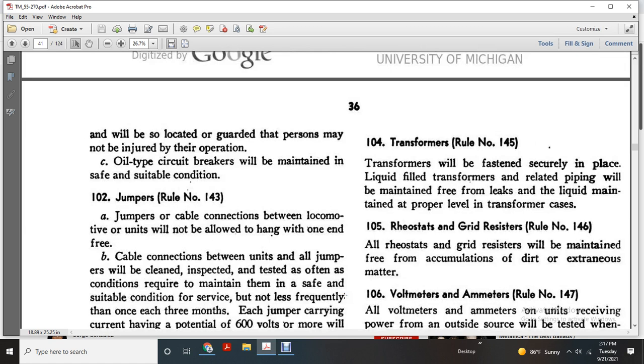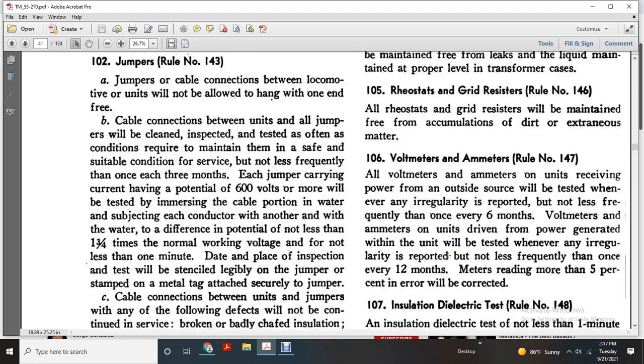104, transformer, rule number 145. Transformers will be fastened securely in place. Liquid-filled transformers and the related piping will be maintained free from leaks. Liquid will be maintained at the proper level in the transformer. The rheostat and grid resistor, rule number 146: the rheostat and grid resistor will be maintained free from accumulation of dirt and foreign matter.